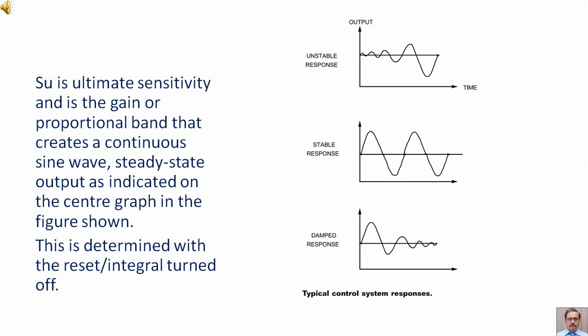S subscript U is ultimate sensitivity and is the gain or proportional band that creates a continuous sine wave steady-state output as indicated on the center graph in the figure shown. This is determined with the reset (integral) turned off.